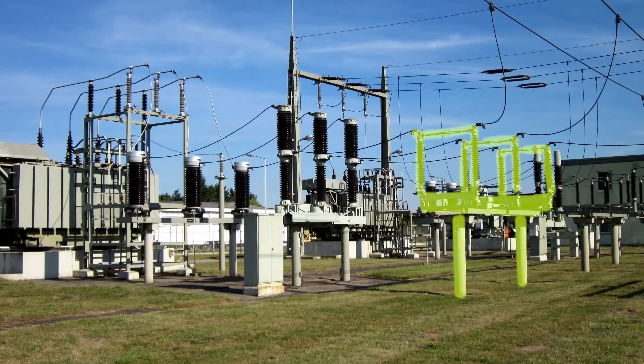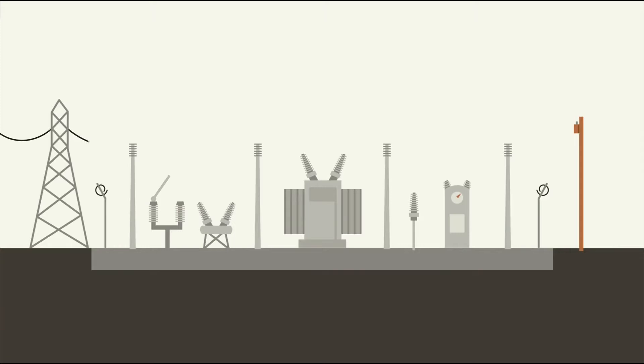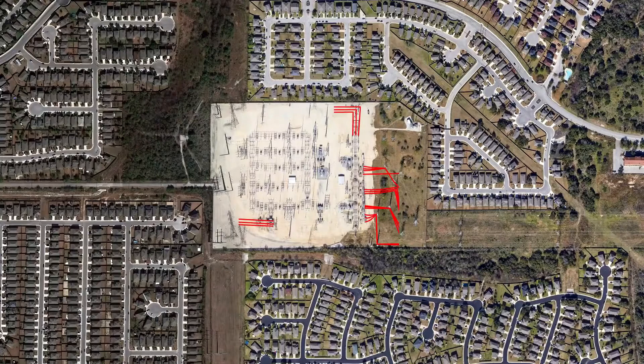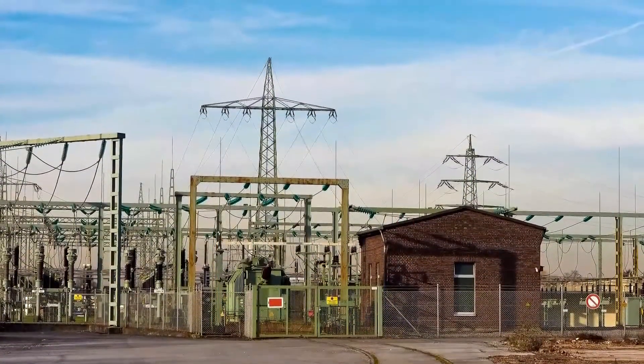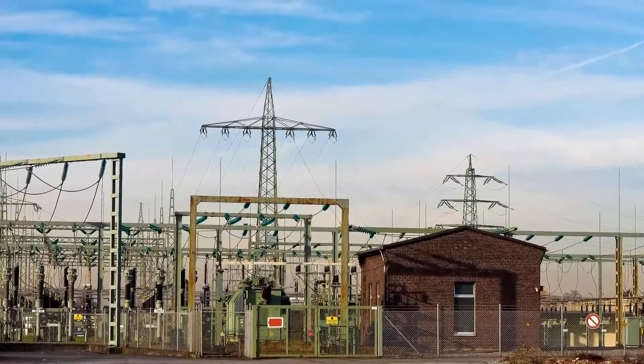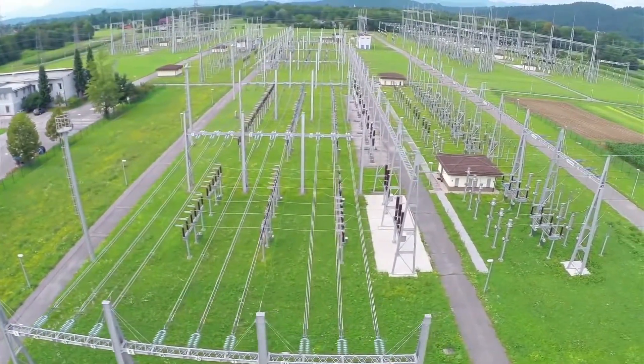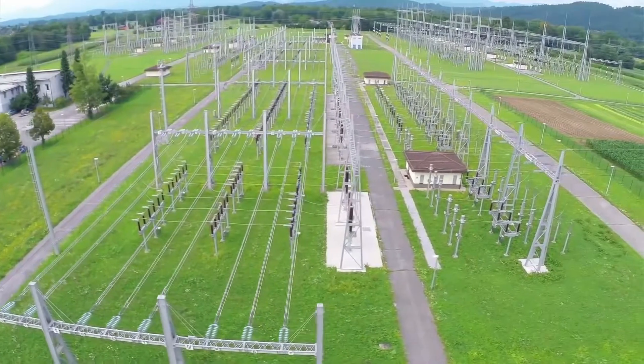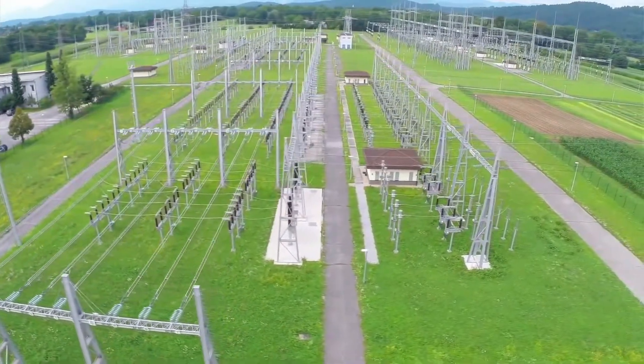The first and often simplest of these roles is switching. The general layout of a substation consists of some number of electric lines — called conductors if you want to fit in with the electrical engineers — coming into the facility. These high voltage conductors connect to a series of pieces of equipment before heading out to their next step in the power grid. As a junction point in the grid, a substation often serves as the termination of many individual power lines, creating redundancy and making sure that the substation stays energized even if one transmission line goes down. The connections to these various devices are called buses, often rigid overhead conductors that run along the entire substation. The arrangement of the bus is a critical part of the design of any substation because it can have a major impact on overall reliability.